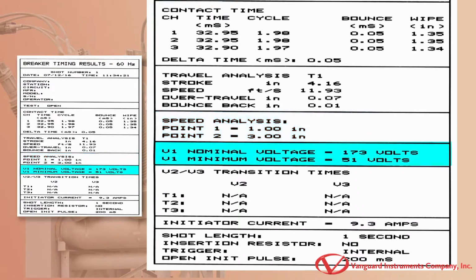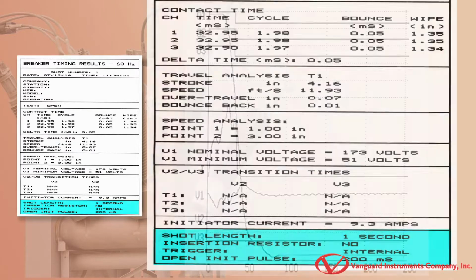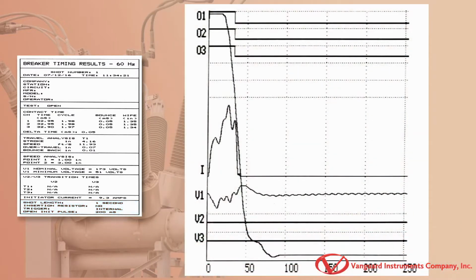The V1 voltage measurement is shown here. The CT7000S3 will detect the on-off voltage transition on the V2 and V3 voltage input channels. It can detect up to 3 voltage on-off events and record the times. The measured open coil current is shown here. This last section shows additional test information. We can see that the shot duration was 1 second, there was no insertion resistor in the circuit breaker under test, and the trigger mode was set for internal trigger. Lastly, here is the graphical printout of the test results.